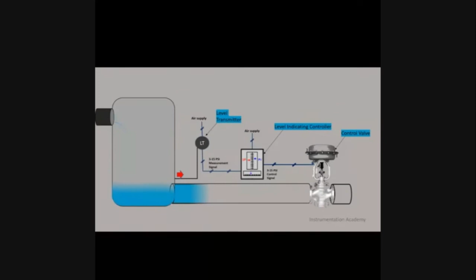This figure explains how instrumentation is applied to control the level of liquid in a tank. The first instrument in this control system is the level transmitter. The purpose of this device is to sense the water level in the tank and report that measurement to the controller in the form of an instrument signal. In this case, the type of signal is pneumatic, a variable air pressure sent through metal or plastic tube. The greater the water level in the tank, the more air pressure output by the level transmitter. Since the transmitter is pneumatic, it must be supplied with a source of clean compressed air through the air supply tube entering the top of the transmitter.